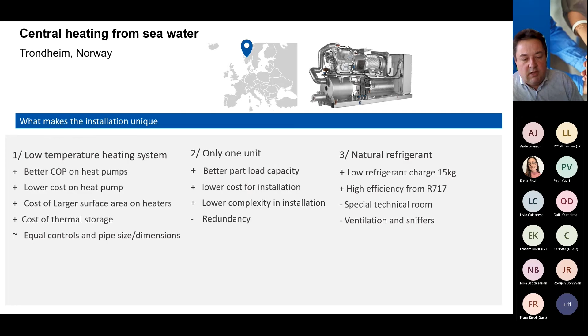And then last, natural refrigerants. At Johnson Controls, we can sell you anything you like in terms of heat pumps: low GWP, HFOs, or ammonia, or hydrocarbons. We have them all. In this case, we actually chose the natural refrigerant. We chose a unit that had a very, very low charge, delivering close to 300 kilowatts on only 15 kilos of ammonia. And that gives us a high efficiency due to the properties of the refrigerant. Of course, it requires a special room, and it requires ventilation and sniffers to install an ammonia heat pump. But that being said, with a charge of 15 kilos, it's not a big task to do that.